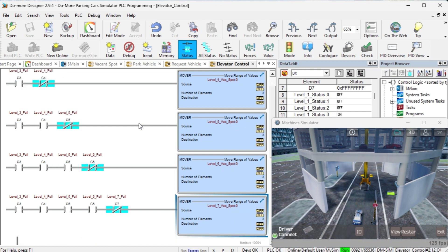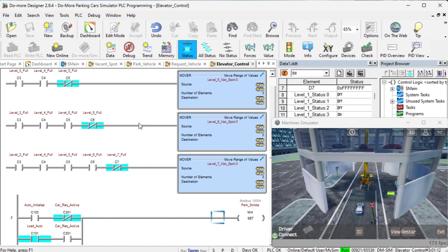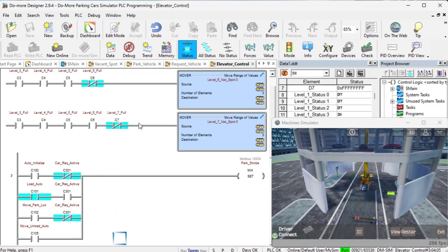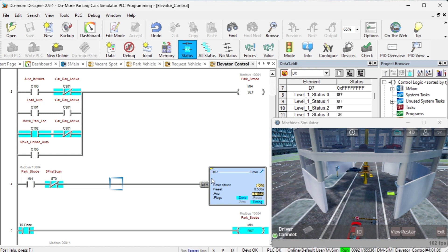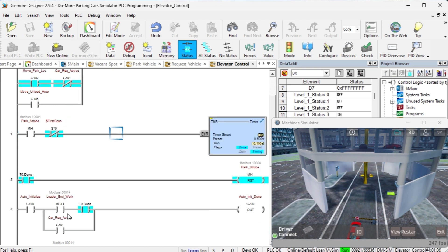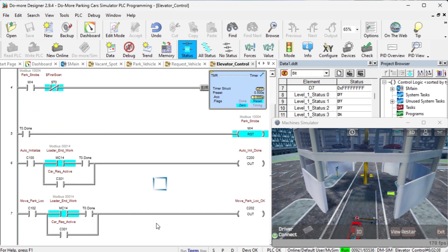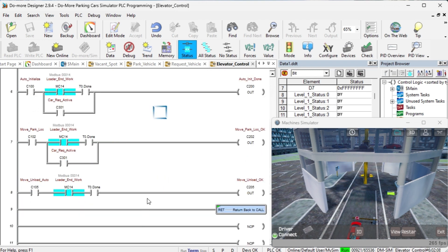The parking strobe will tell the elevator to move. A timer is set for half a second for the signal of the parking strobe. This will allow the easy PLC machine simulator to see and activate the signal. The step complete for the elevator movement is done with the following rungs. If a car is requested, the auto initialize and move to park location is bypassed.